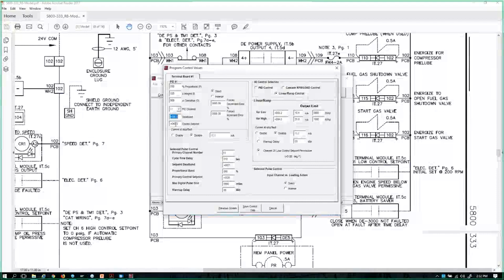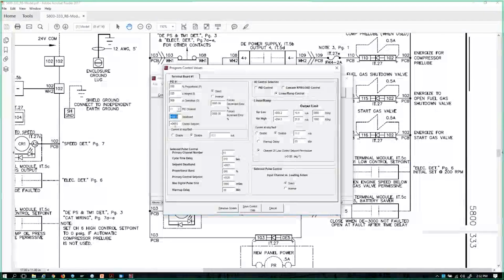So 40 psi is my control set point. I want to give it no more than 40 psi for my suction pressure. So if the pressure crosses above 40 psi, it's going to try to close. If it drops below 40 psi, the further it drops, the more that valve's going to open up, trying to maintain 40 psi. So if I select a 1 pound deadband in there, from 39 pounds to 41 pounds, there will be no movement and no adjustment made to this valve.